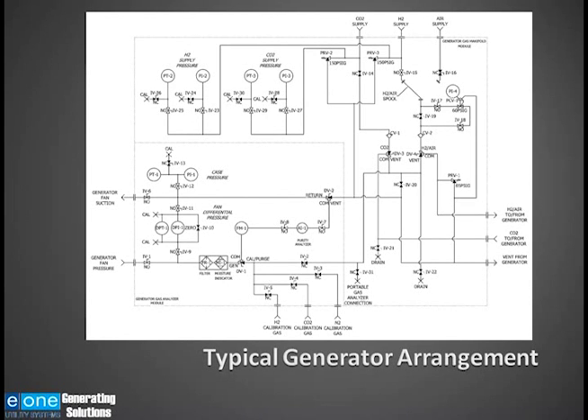As you go down the hydrogen line, you can see that we have a pressure control valve. This is used to maintain pressure in the generator. This is either an automatic operation if IV 17 and 18 are open, or it can be a manual operation when 17 and 18 are closed and 19 is open. And then as you get down, there's two three-way valves that are used to put hydrogen and CO2 into the generator and air into the generator.